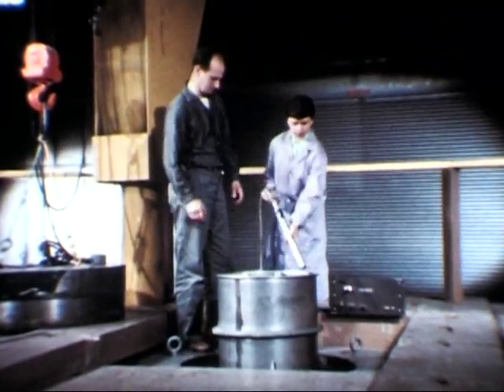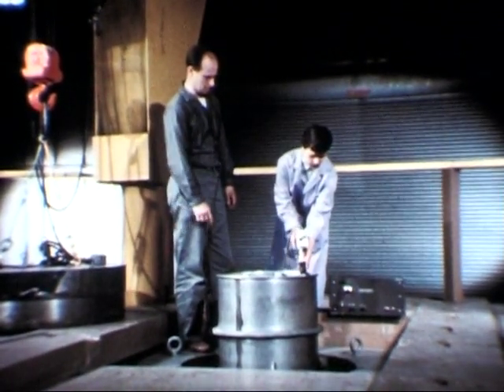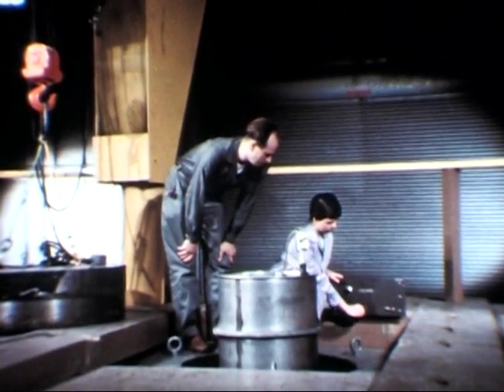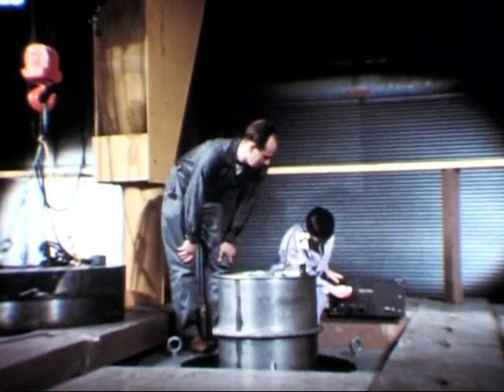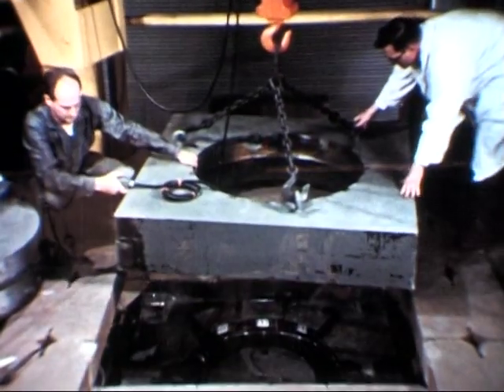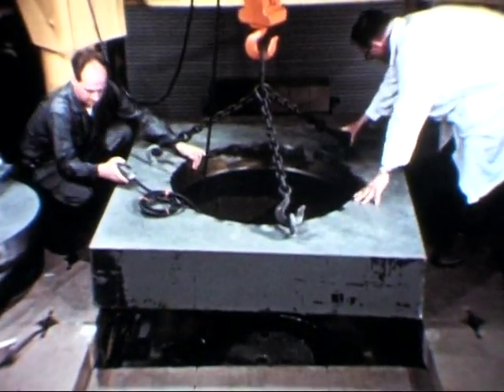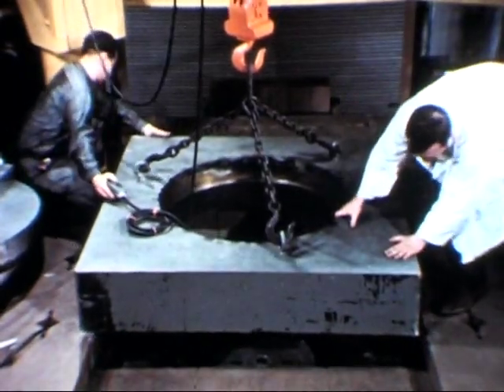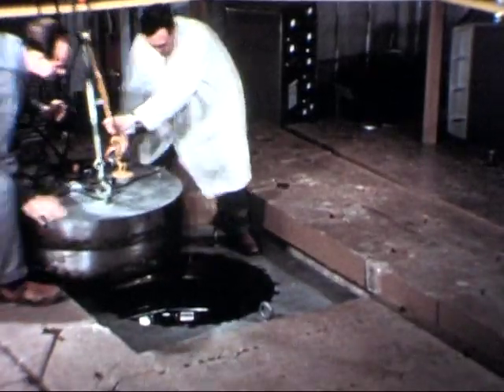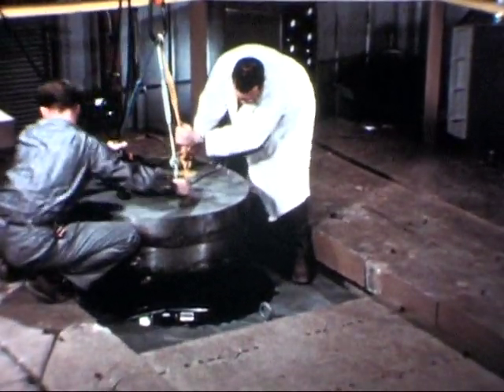Neutron migration experiments can be performed on the top of the system. For these purposes, approximately 10 to the 7th thermal neutrons per square centimeter per second can be furnished at the bottom of the exponential assembly. The five-foot square central region of the reactor is covered by a steel-jacketed concrete slab one foot thick. The concrete is the high-density type weighing 250 pounds per cubic foot, and this is the only place in the Argonaut where high-density concrete is used.